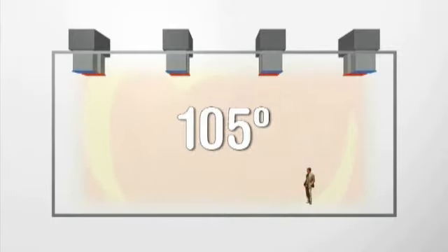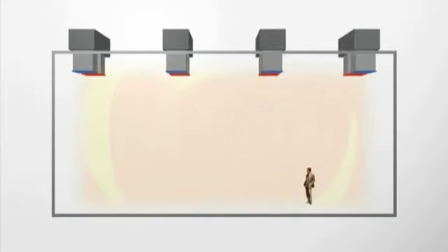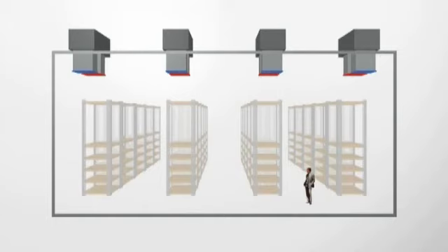So our objective is to only have air conditioning in your building from ground level up until 8 feet maximum. That's it. We're going to leave approximately 80% of the store not air conditioned. The manner in which we're going to do this is we're going to extend down the ductwork of your air conditioning system. At present, the return air duct drops approximately 1 to 2 feet below ceiling level. We're going to take this duct down to a height of approximately 7 to 8 feet.